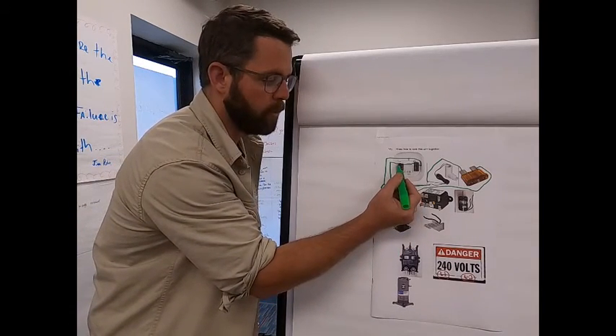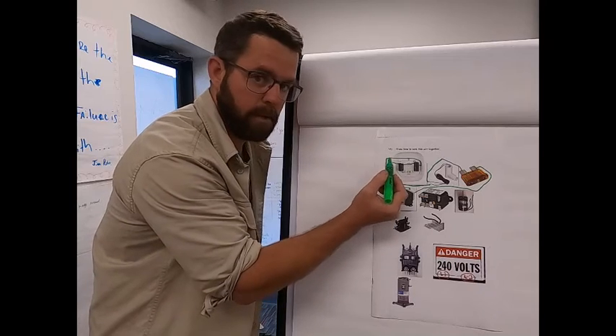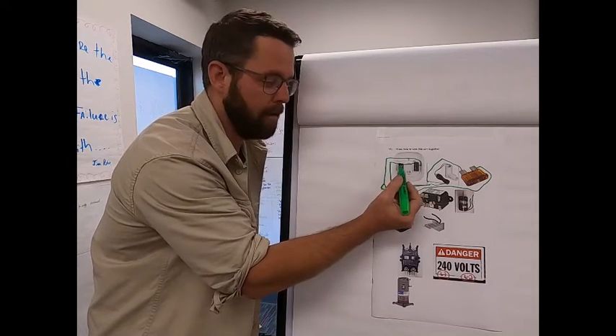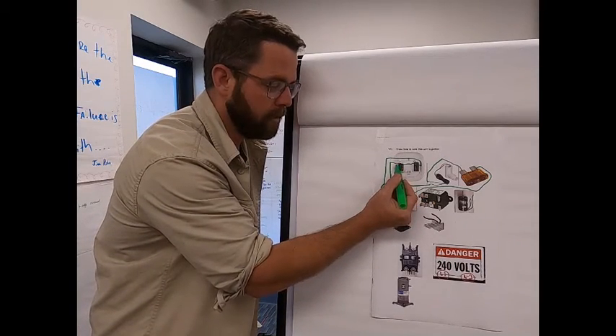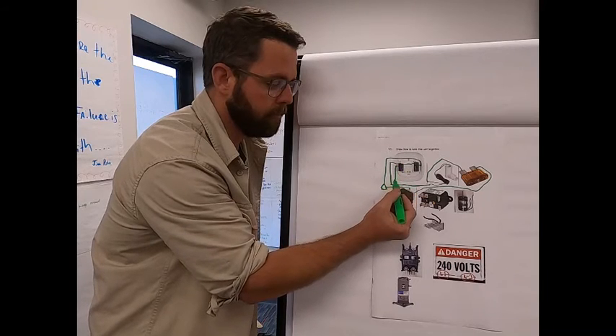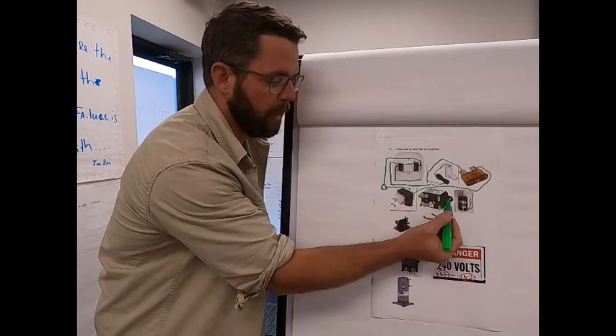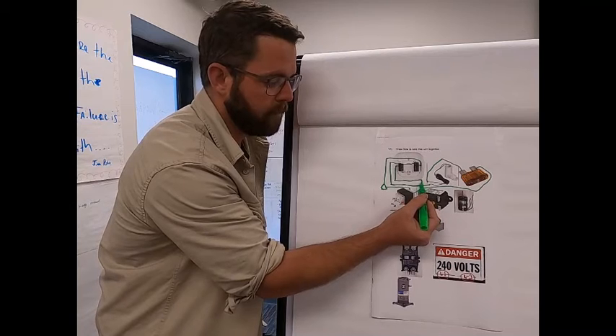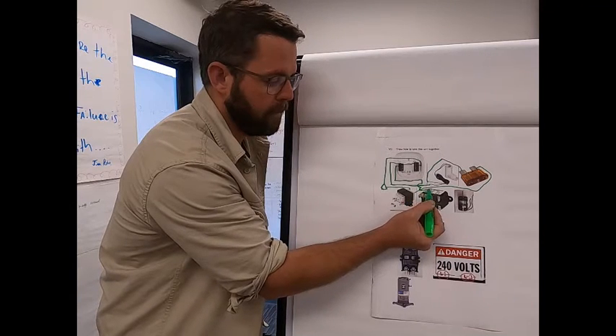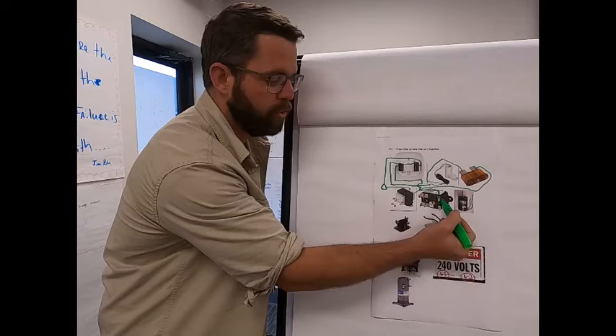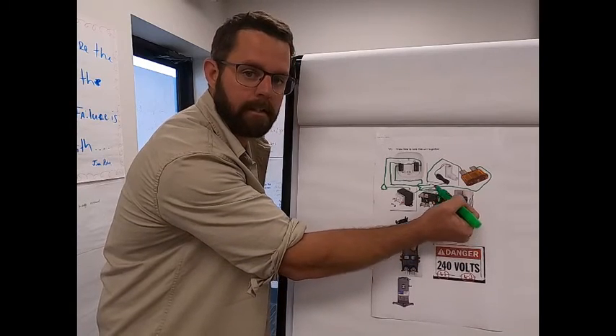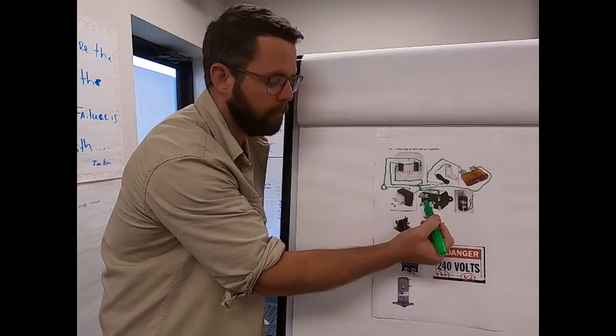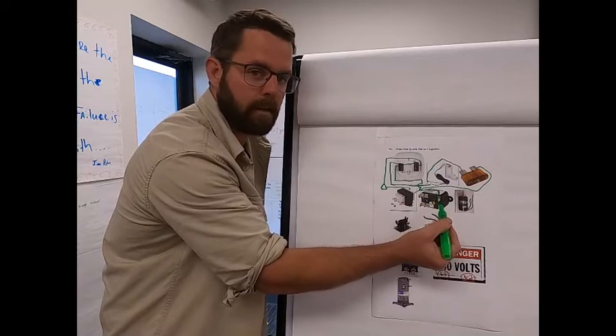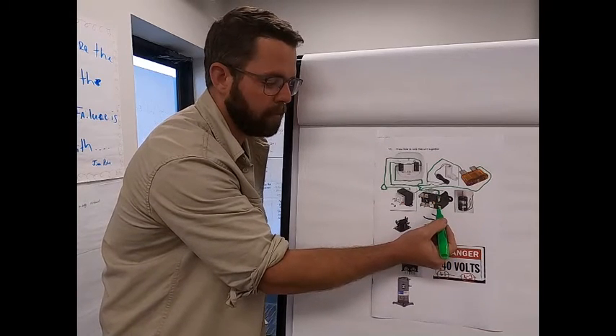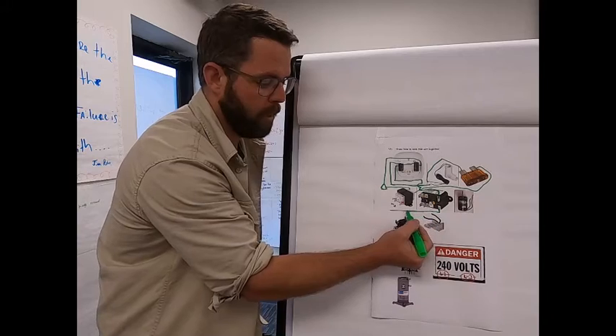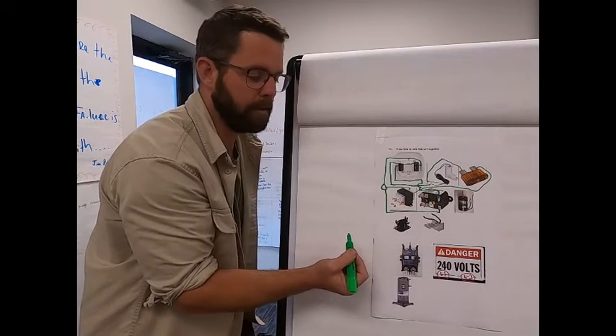Next, we're going to use the G wire. The G wire is for your fan. G is going to leave the thermostat, come over towards the blower relay, which is depicted here, and connect to one of the two standalone pins. These standalone pins are your coil. The other side of the standalone pin will need common. So we can run to our wire nut that we already built here.